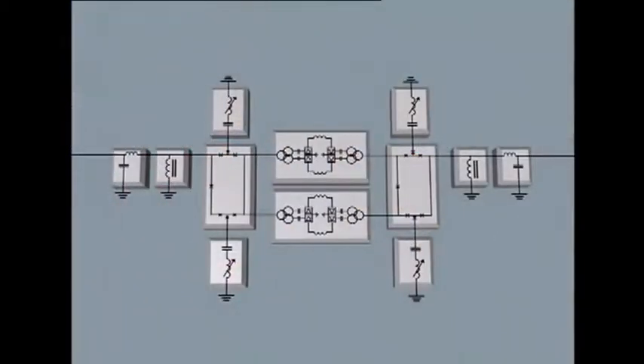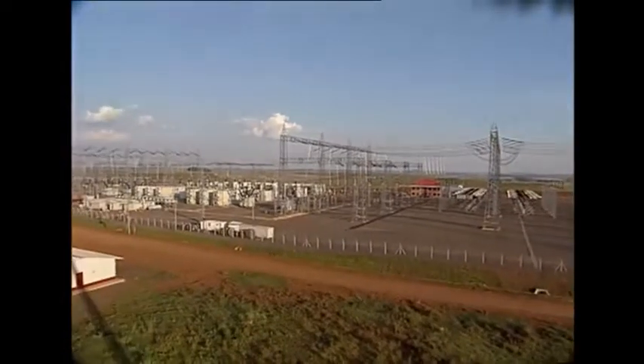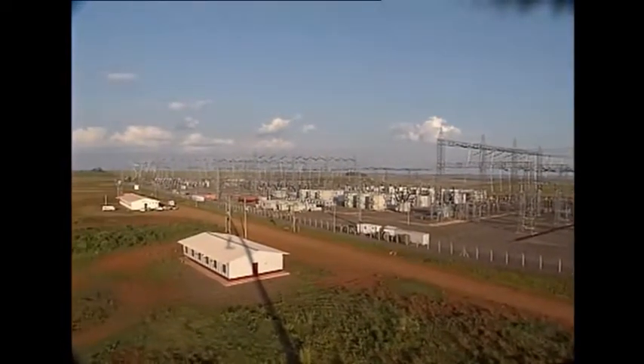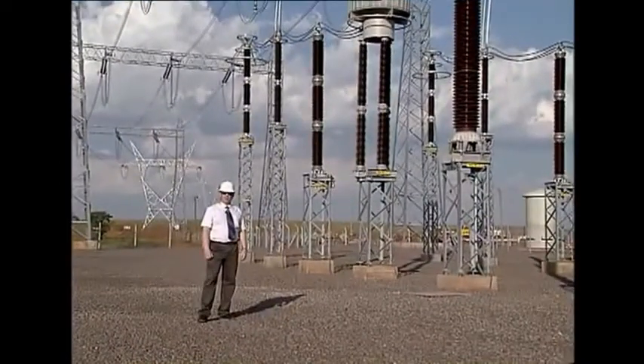The equipment described is on the 50 Hz side. The equipment on the 60 Hz side is similar, except for the line reactor which is rated at 250 megavar. We should also note that this reactor also works as an auxiliary power transformer. This is the outgoing 525 kilovolt AC bus on the 60 Hz side.